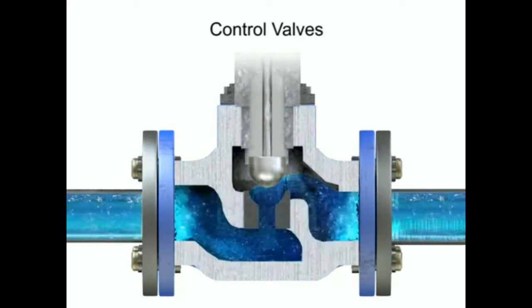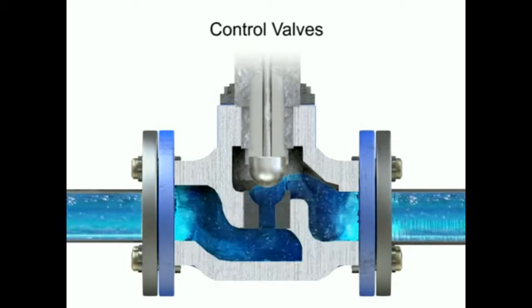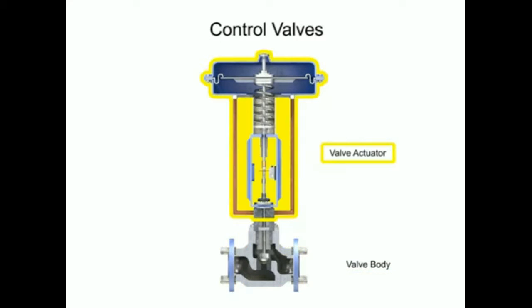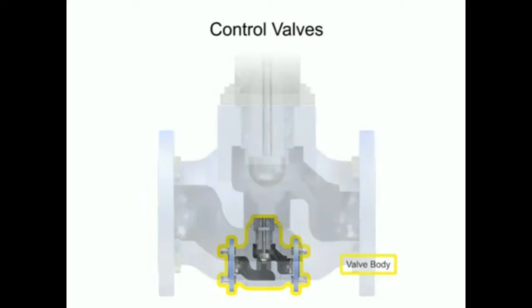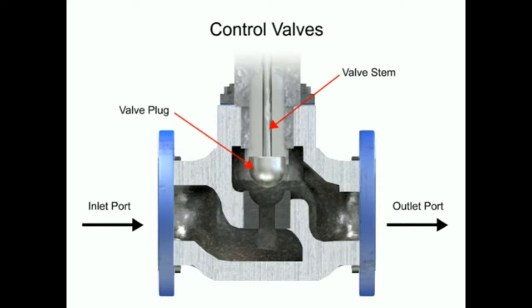Valve actuators control fluid in a pipe by varying the orifice size through which the fluid flows. Control valves contain two major components: the valve body and the valve actuator. The valve body provides the fluid connections and a movable restrictor comprised of a valve stem and plug that is in contact with the fluid to vary the flow. The valve actuator is the component that physically moves the restrictor to vary the fluid flow.